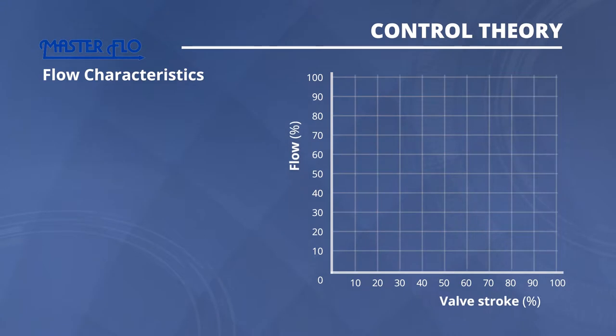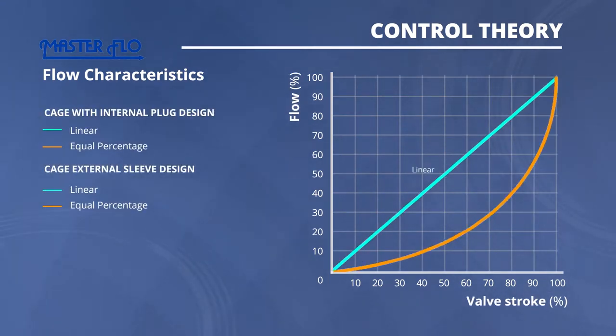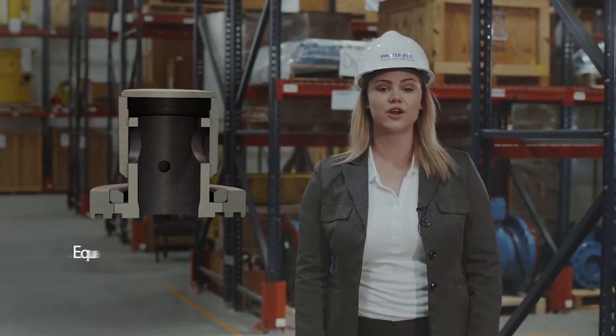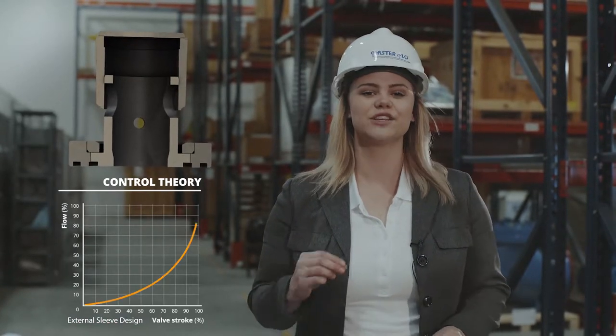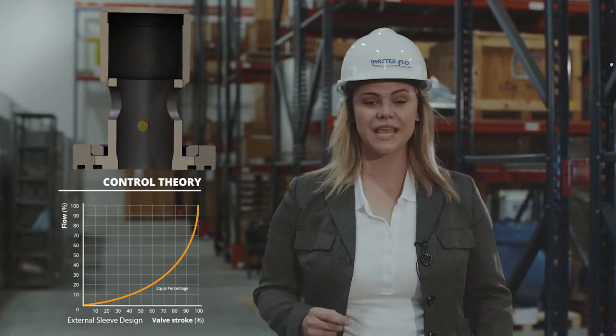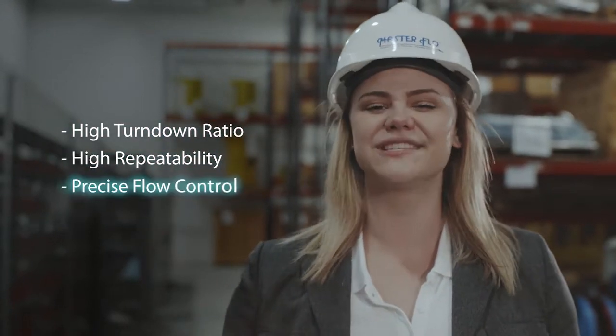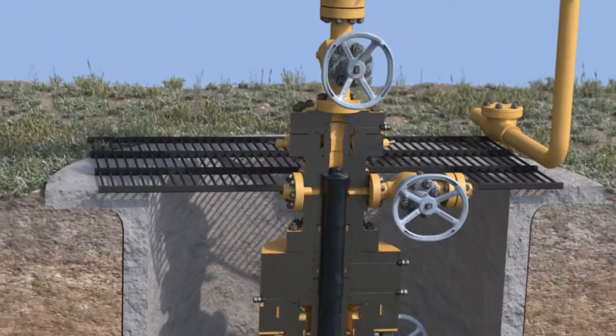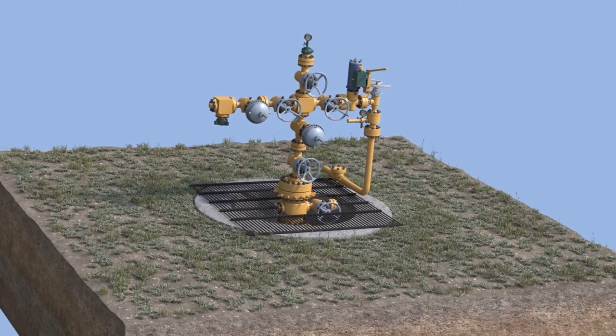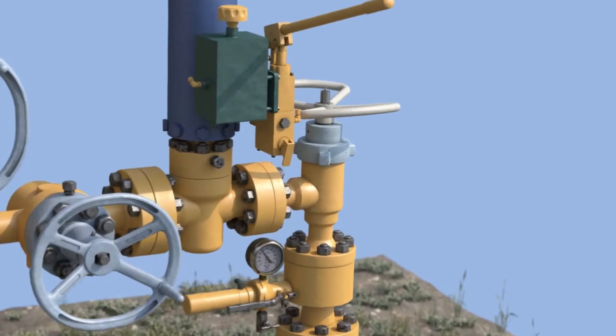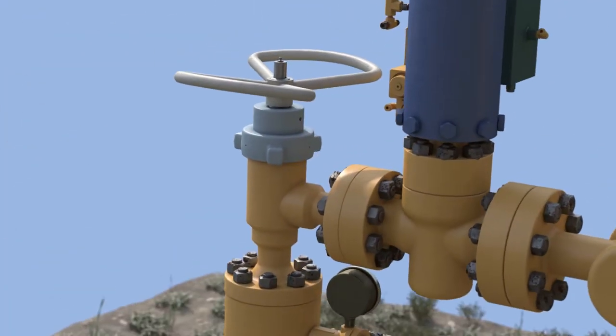The cage with internal plug and external sleeve choke valve designs are both characterized by equal percentage or modified parabolic control. They provide a gradual response in the lower portion of stem travel, delivering a high level of initial control, which brings the well on stream. As the valve is opened and the flow increases, this level of control is maintained throughout the stem travel, resulting in high turndown ratio, high repeatability, and precise flow control. This is imperative because a well-controlled flow allows you to ramp up your well slowly. A rapid well ramp-up can destabilize it, potentially causing a collapse and reducing the well's productivity index. Avoiding damage to your most valuable asset — the reservoir — is crucial.